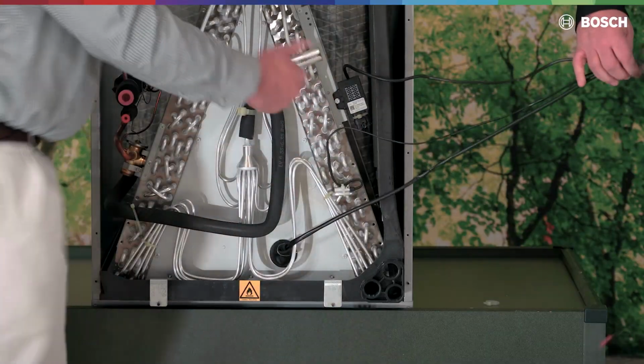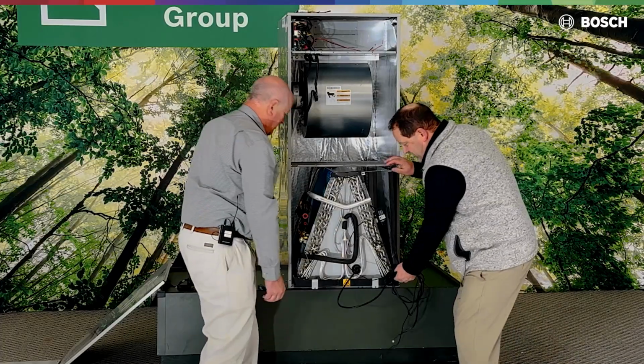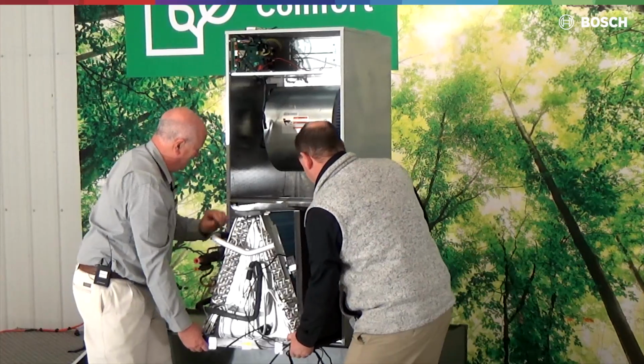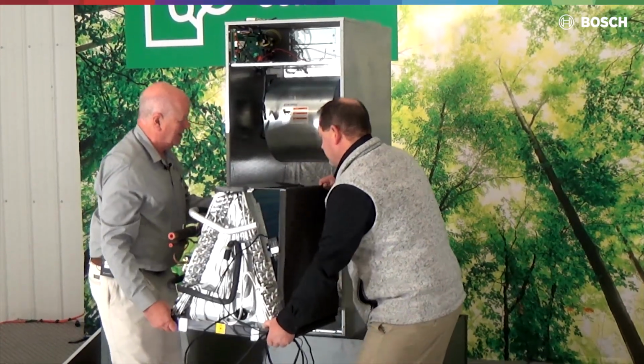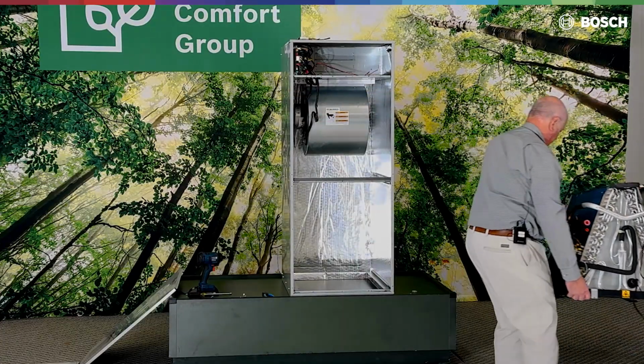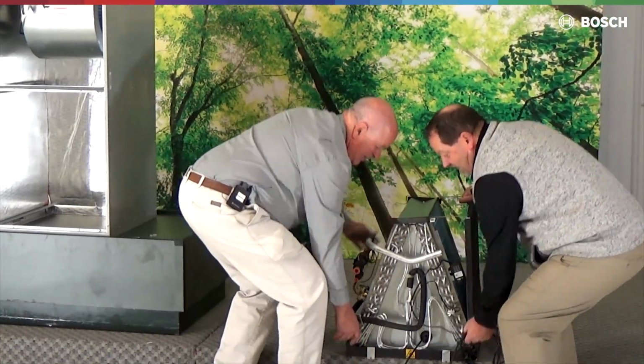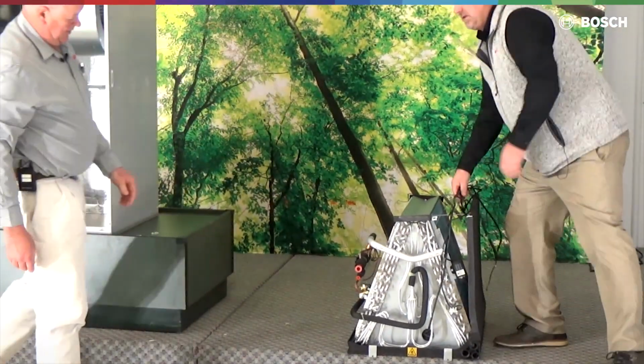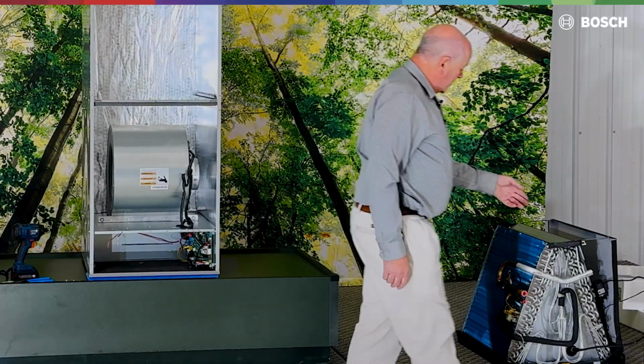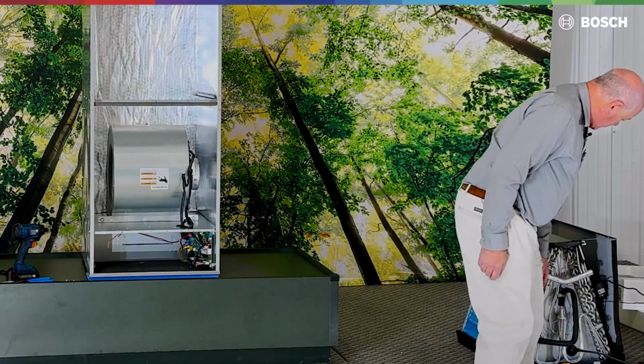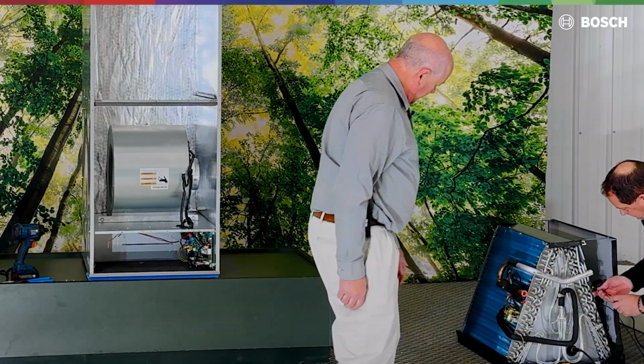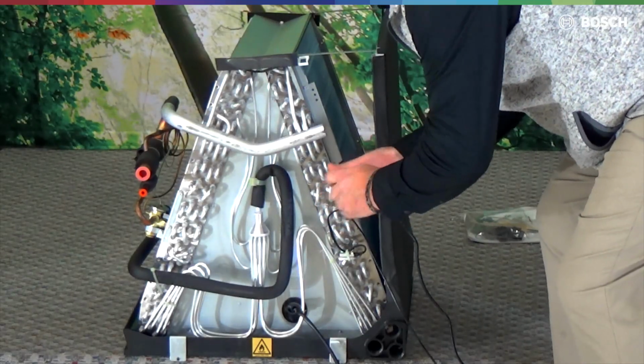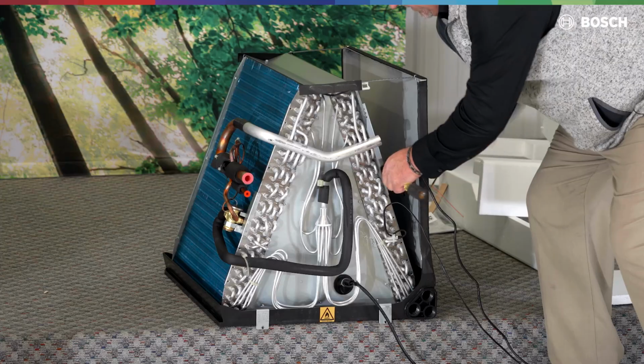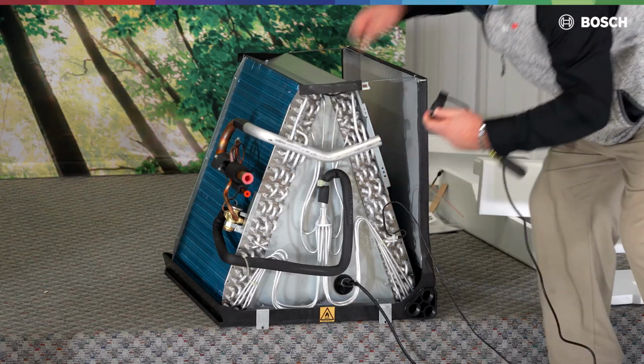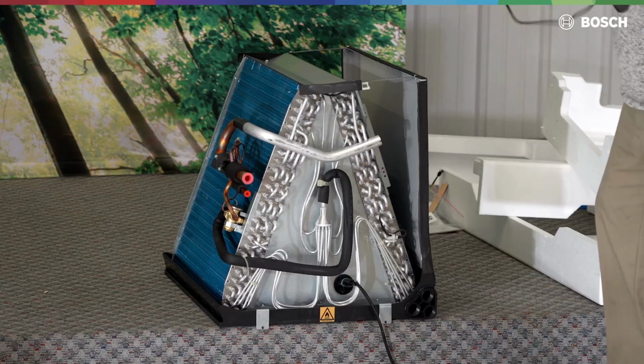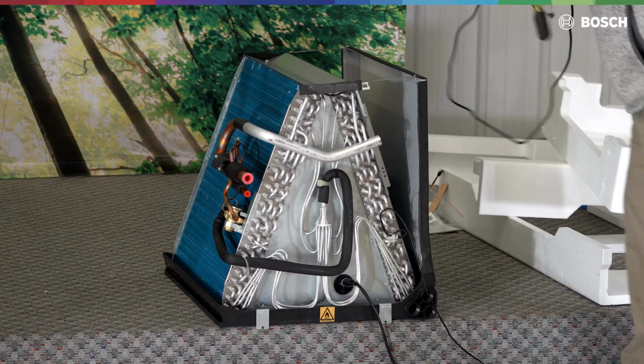So we're going to slide this out. Chris, I'm going to ask you to give me a hand just because I'm old and decrepit. These things are actually kind of heavy. So we're just going to set that off to the side, and we're going to leave it there until we flip the furnace upside down. So Chris, we have to take that sensor off so we can put that coil in. Would you be so kind to do that for me, sir? Looks like it's just mounted with 1 screw. That sensor comes off, and we'll relocate that inside the unit once we slide the case coil back in.